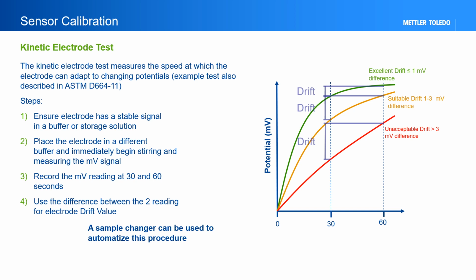Step 1 is to ensure an electrode has a stable signal in a solution by measurement or just allowing it to stand in a solution for a couple of minutes. Next, the electrode is moved to a solution that yields a different potential, such as one pH buffer to the next, or different redox potential solutions for a redox electrode. Immediately start tracking time from the solution change. After both 30 and 60 seconds in the solution, record the raw millivolt values. You can gauge the electrode's response speed from the difference in these two values. This value is referred to as the drift.